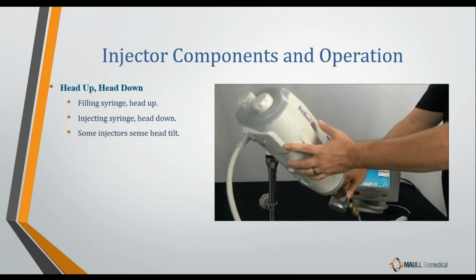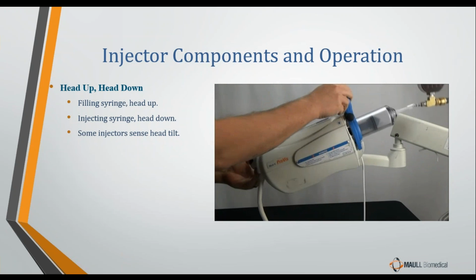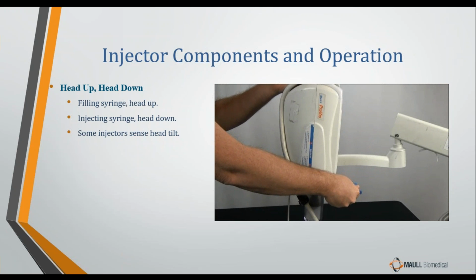Now once it's primed, and we're going to inject the fluid into the patient, the injector head is always tilted downward. It has to be at least 30 degrees below zero. The obvious purpose of this is if there is any air left in the syringe, then those air bubbles should float to the non-business end of the syringe and not get injected into the patient. Now some injectors, some models, the Mark 7, the Angiomat Illumena, the OptiVantage, can actually sense the head tilt position. Not all injectors do that, but some models do. The system can actually tell if the injector head is not tilted below 30 degrees horizontal. Depending on the model, some of them will just warn the operator, hey, you haven't tilted the head down far enough, and give the operator the option of bypassing it, saying, I know, I want to shoot it anyway, or some models will completely inhibit the injection until the injector head is tilted far enough down.